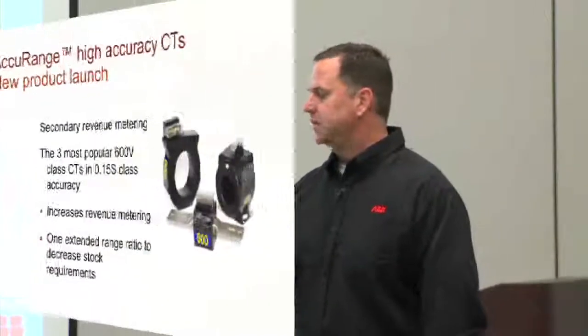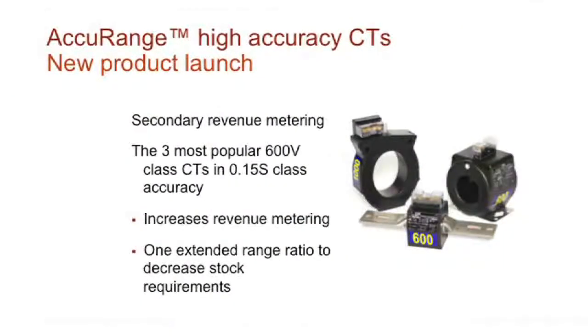The utility can save, it might be a very small percentage. You say, okay, well, if we go from 0.25 to 0.05, that's a small fraction. Well, when you're dealing with some of the larger applications and larger utilities which have a lot of metering on their units, this can add to a very significant amount of money on a monthly basis. Let's talk about the different applications where we would find these highly accurate CTs. We're releasing a new product this week at Automation and Power World called the AccuRange current transformers. We have 3 different types that are coming in.